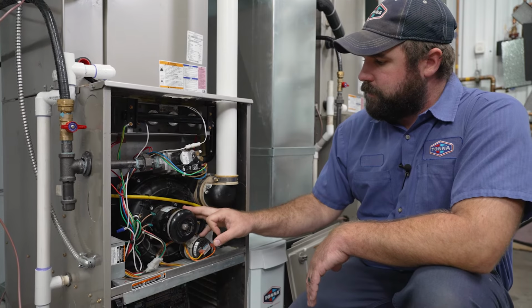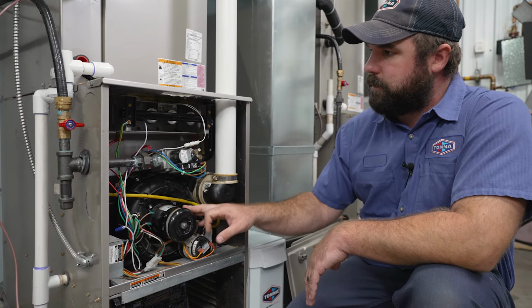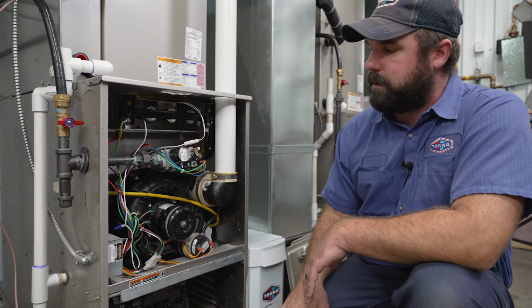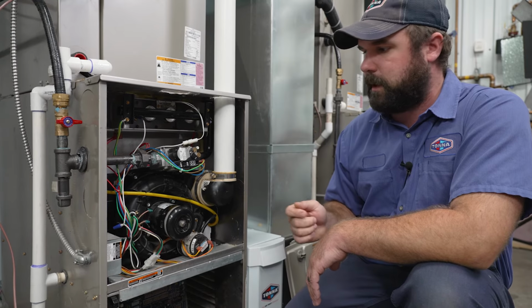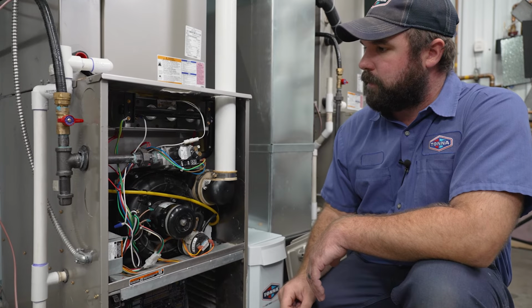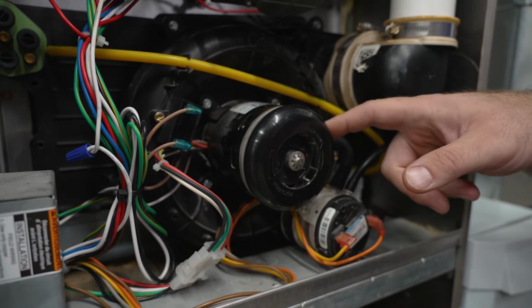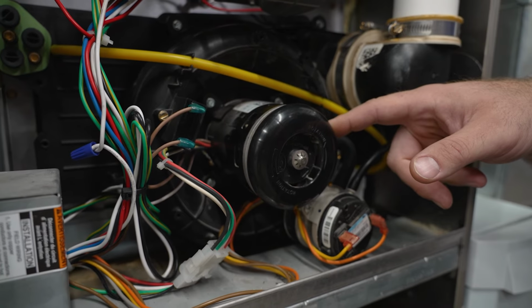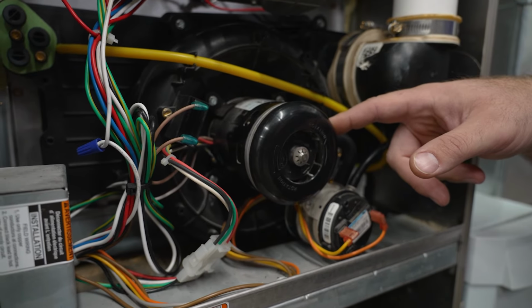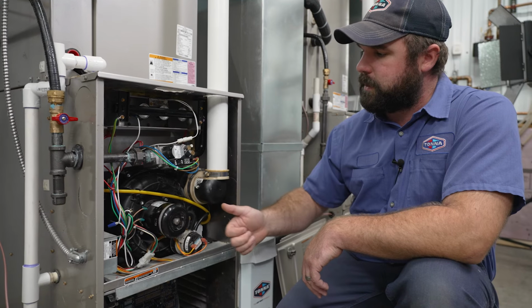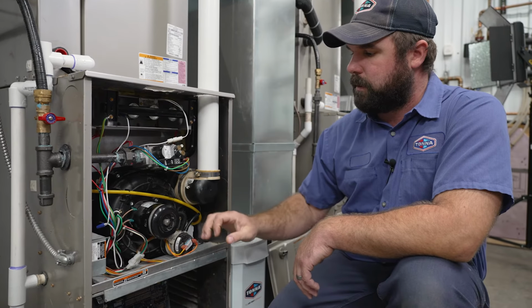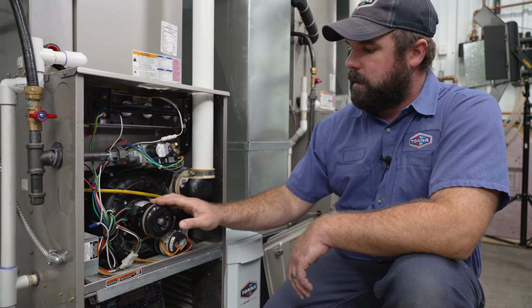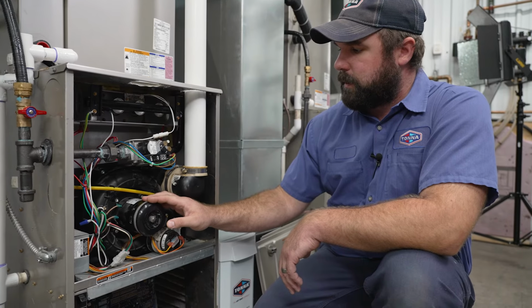This is your inducer motor. This is what pulls the flame through the heat exchanger. Most heat exchangers are kind of like an S shape, and you won't be able to visually see that, but this pulls the flame and gases through the heat exchanger and then exhausts those gases outside. So we want to make sure that it's not noisy and is running smoothly too.